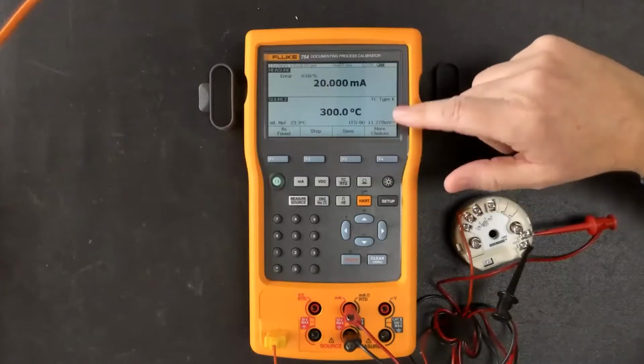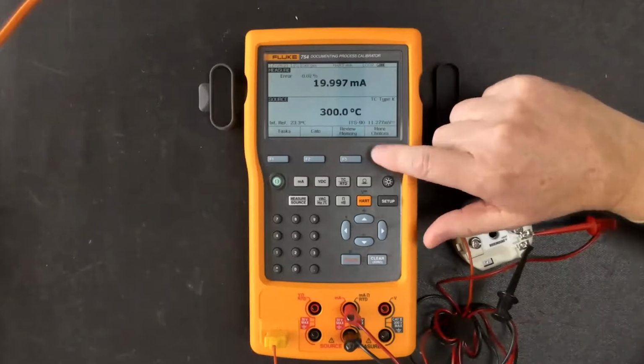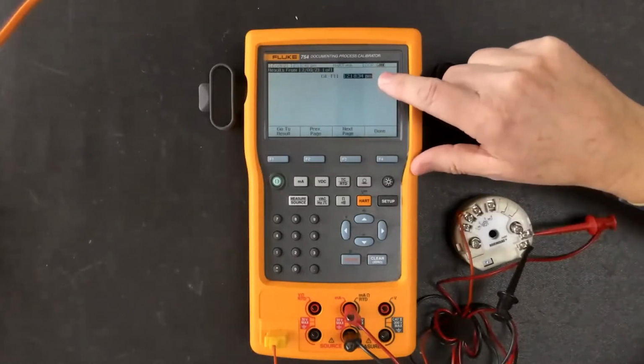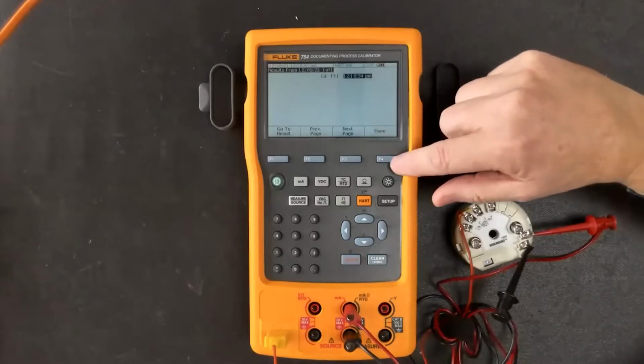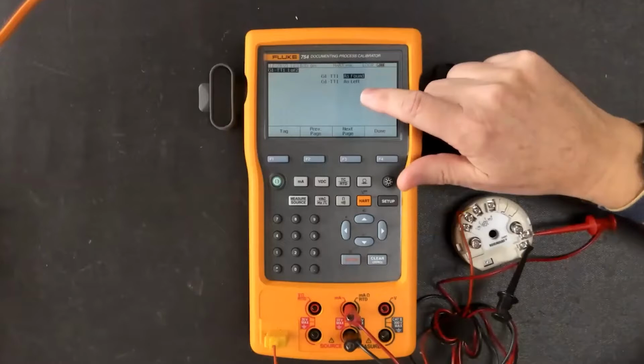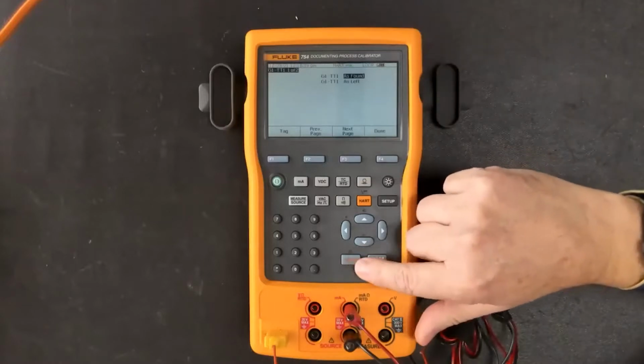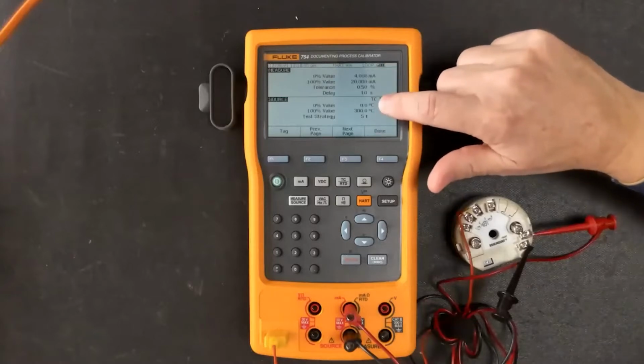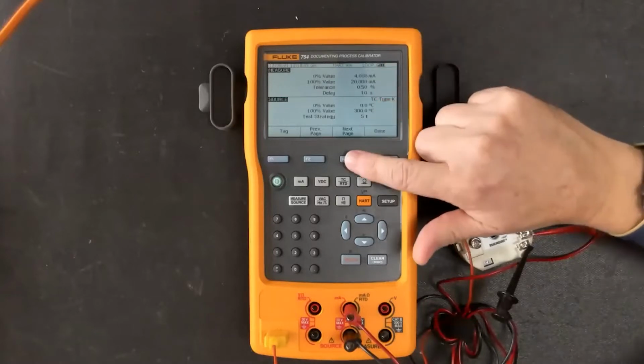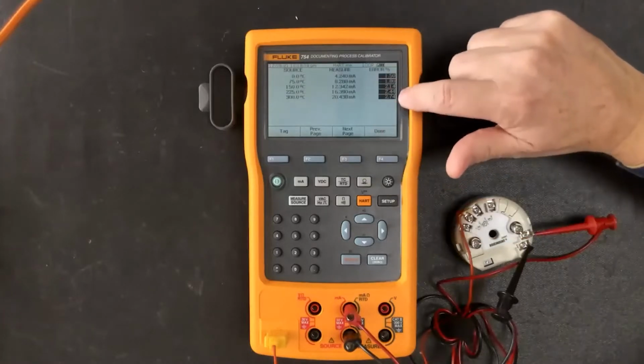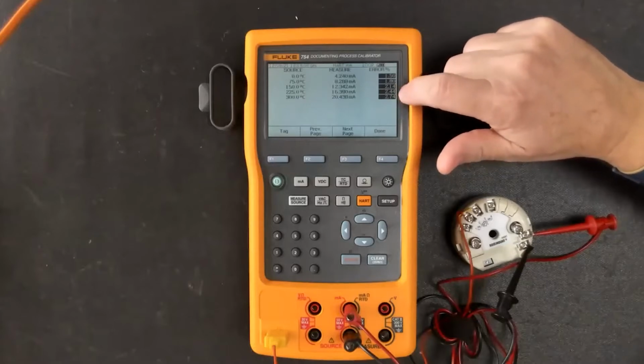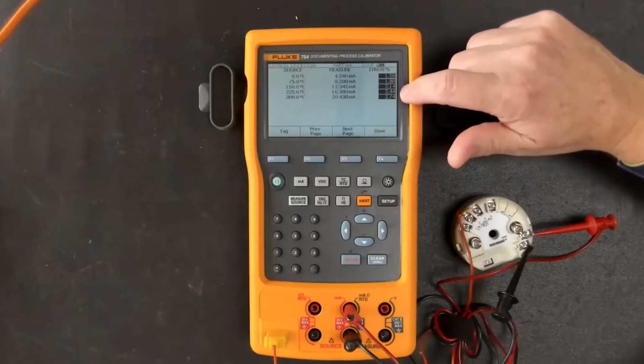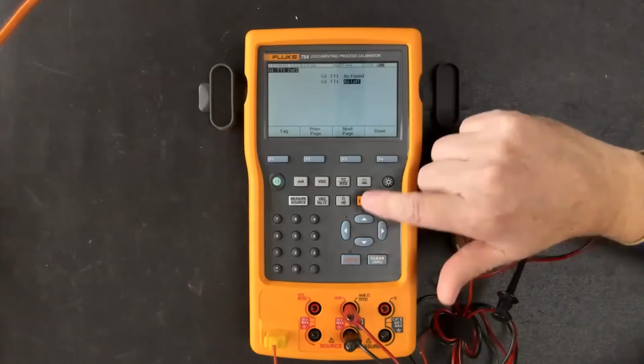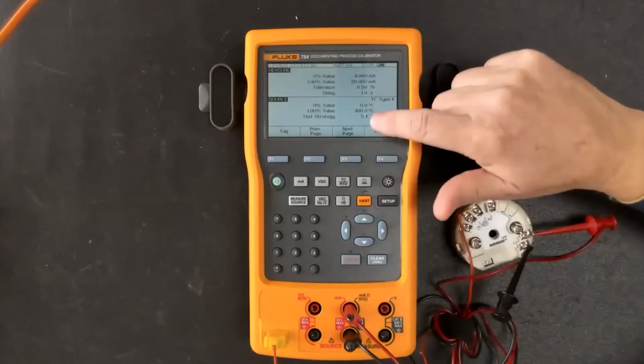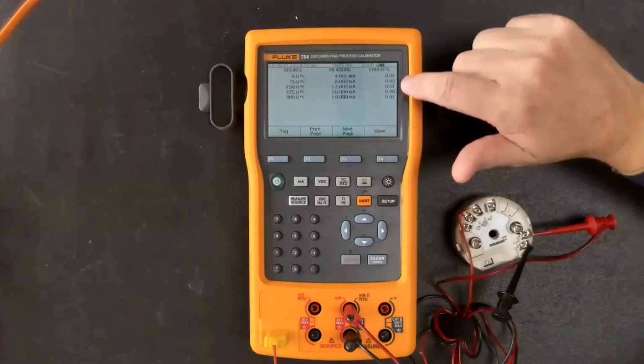So now that information has been captured into the calibrator, and if I review memory, you'll see here's that calibration result. Now remember the report that Mike showed you. If we look at this, we have our as found and as left results. I'll enter in on the as found, and you'll notice here's all that configuration information that you see in that calibration report. This gets saved, and then if we go to the next page, you'll see that as found data. So here's all that stuff that was out of spec, and this gets documented, saved to the software, so it can be reviewed later. You know, wow, this thing was out of spec when you first went out and looked at it. When you're completed, then you go down to the as left, and again, this gets captured as well. You'll see here's the configuration information. Go to the next page, and there are your as left results.